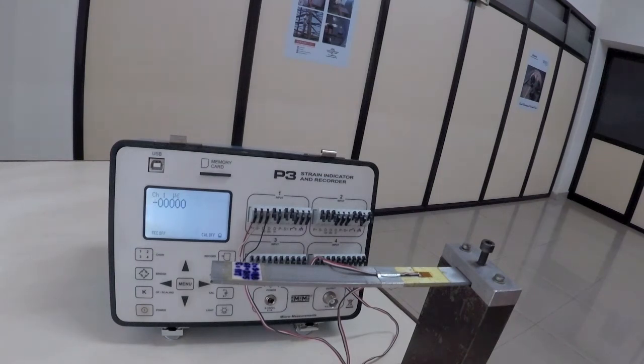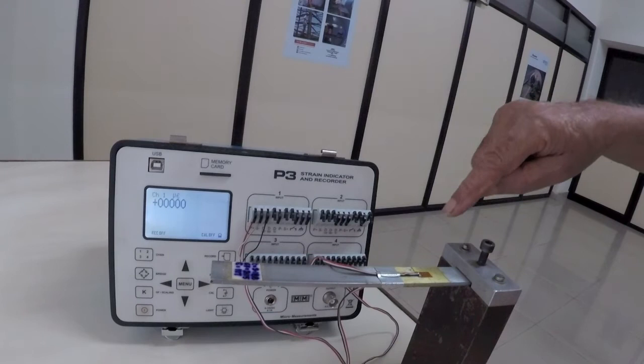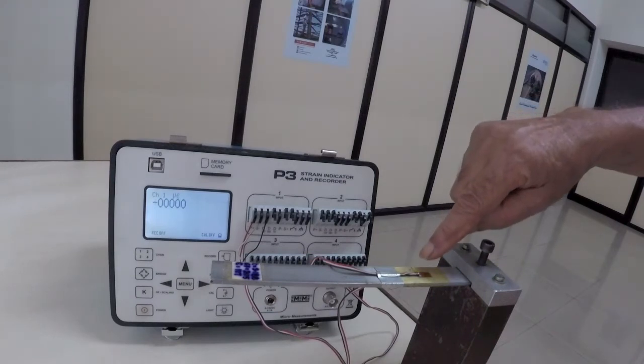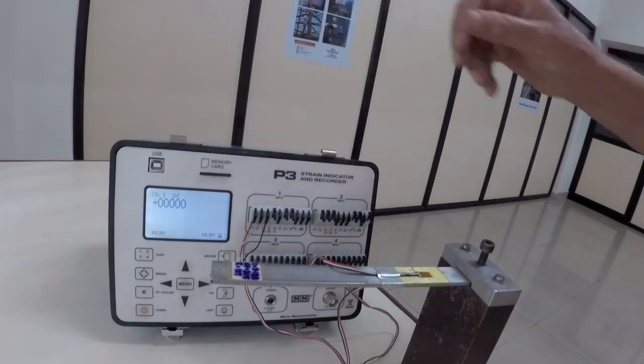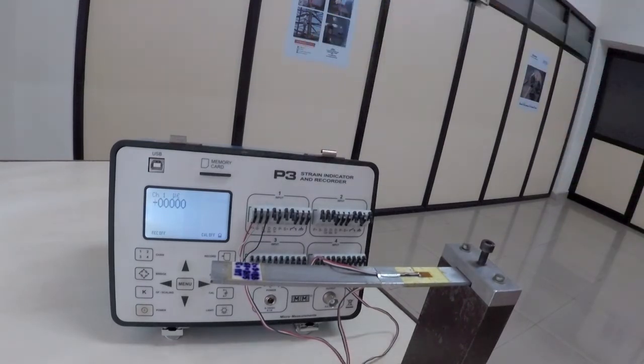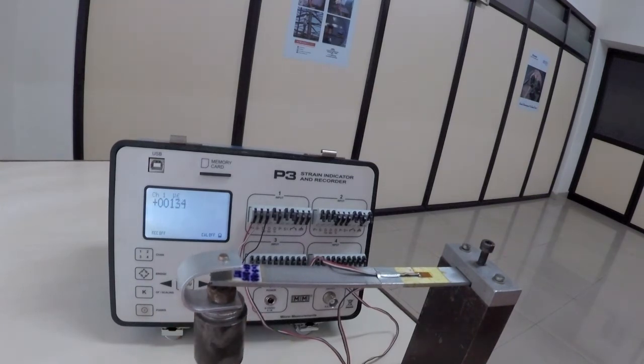Practical example: one gauge on the top surface of a cantilever beam is connected to a Micro-Measurements model P3 strain indicator as a quarter bridge. The instrument completes the bridge internally with high precision resistors, and when the beam is loaded, it displays the output from the strain gauge directly in terms of microstrain.